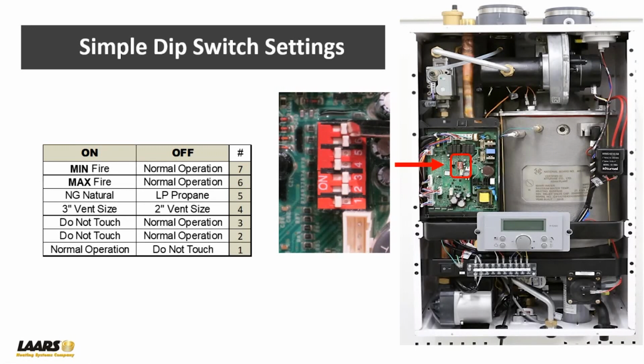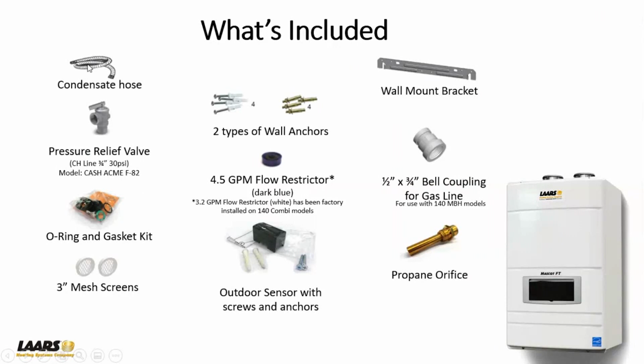However, keep in mind, you do have to do a combustion analysis on any manufacturer's product over 84%. Venting on this, vent material, I will talk about it later, but PVC, CPVC, or polypropylene right off the top. What's included? We also give you a condensate hose for condensate. I strongly suggest utilizing this hose. There is a vacuum breaker right on it, and if you decided not to use it and maybe plumb your condensate in PVC, make sure you have some type of vacuum breaker on it, such as put a T-fitting in and a little riser. That way you're not backing up the condensate and going off on an error code.